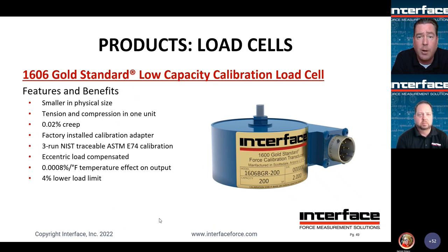Reference standard load cells, we've got a very wide range across a very wide force range as well. Let's start at the low end here and then work up. This is our model 1606. This is a precision version of our model 1500 essentially, so it's going to have additional gauges to provide better moment or off-axis loading rejection. It includes an ASTM E74 calibration, tighter temperature and moment specifications than our standard 1500 would have, and we also guarantee a 4% lower limit factor per ASTM E74 on these load cells. So if it's more than 4%, it does not ship. Other details, you'll notice it's got a slightly larger connector on it than our normal load cells would have. That's an 8-pin connector, and that has separate sense leads that go directly to the bridge for further error reduction. Slide, please.